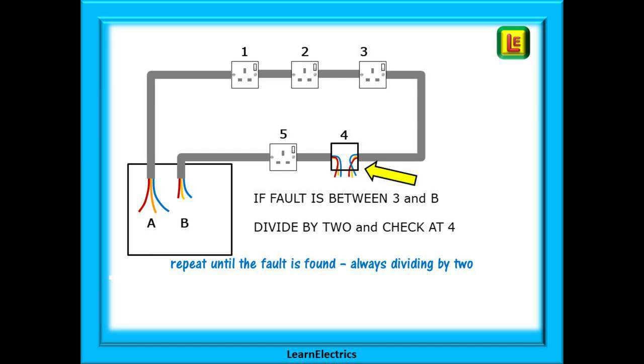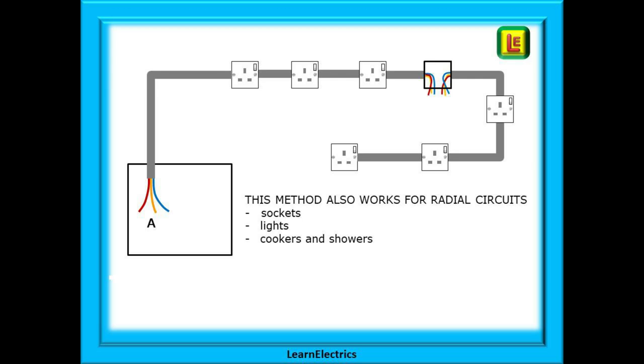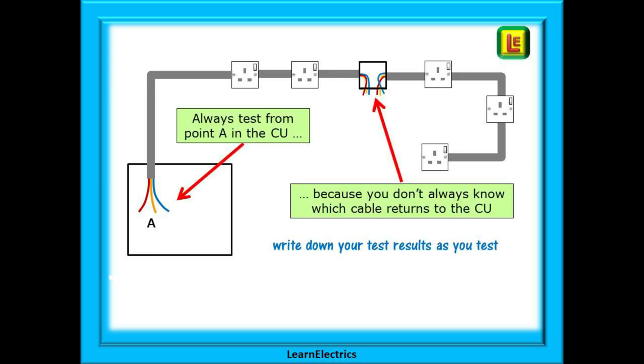Repeat this divide by two until you've narrowed down the problem to just one cable — hopefully it is now easy to spot your problem. We've shown here a ring circuit but it works just as well for radial circuits, radial sockets, lighting, cookers, showers etc. It is an excellent fault tracing method. Always be consistent and test from point A in the consumer unit each time, and write down your test results as you move around the circuit. I also quickly sketch the circuit to help me understand the layout. If you write it down you don't need to remember it — just remember where you wrote it.